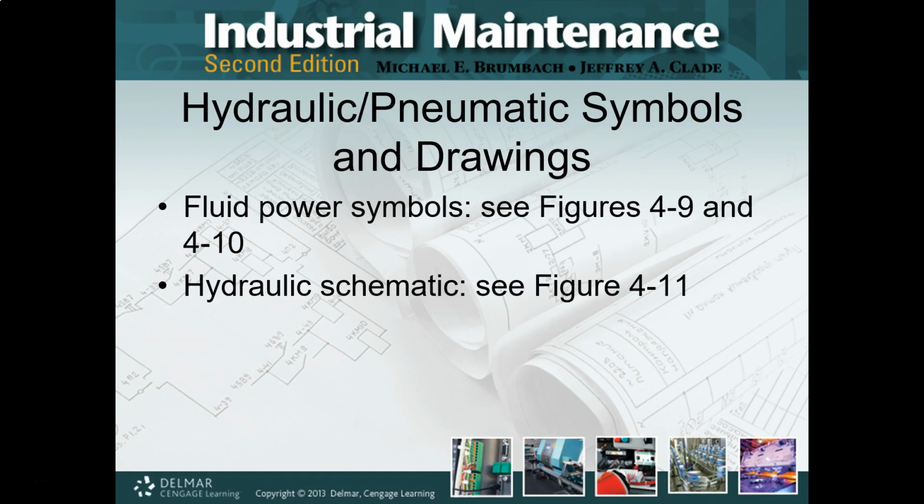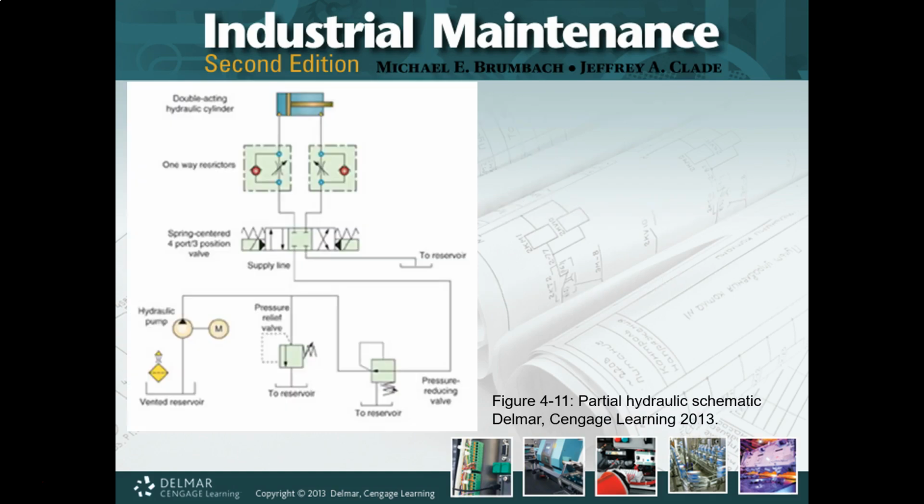We used pneumatics for controlling of valves because we could have all the electrical stuff in an explosion proof box, and then have the airlines run out of that box to the valve, and the valve would do its magic and allow the process to be controlled. At the same time, everything is safe, and the presence of oxygen was not detrimental to the process.